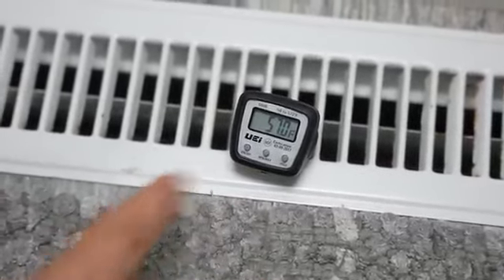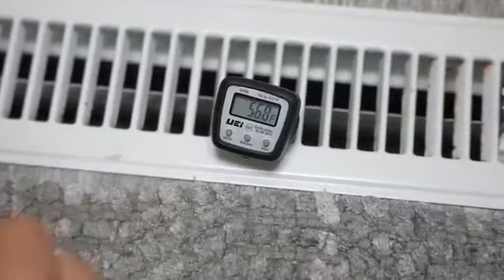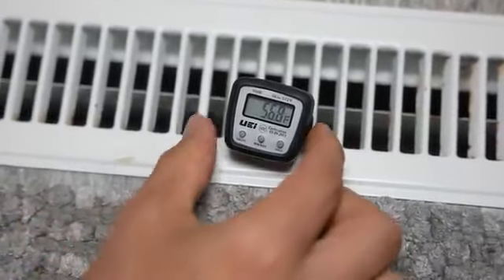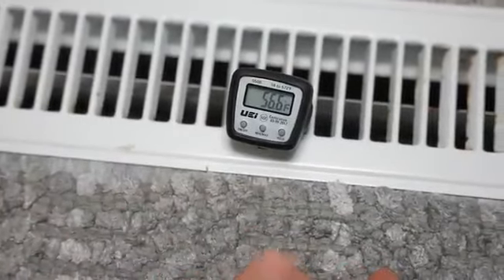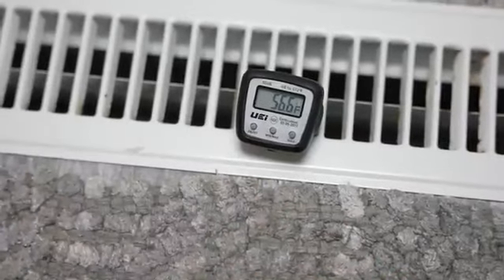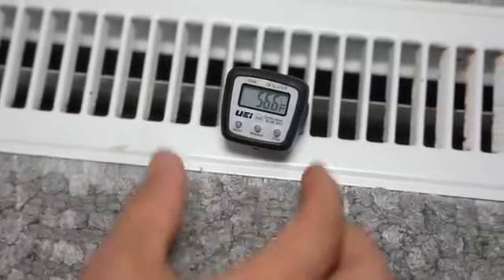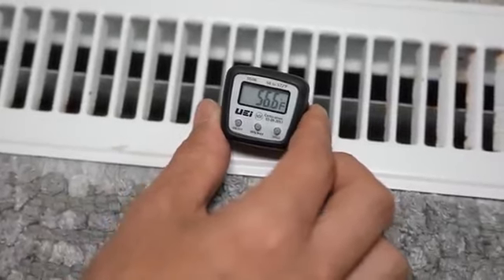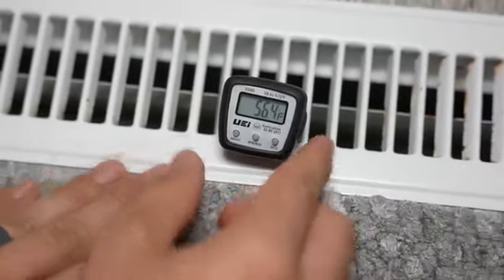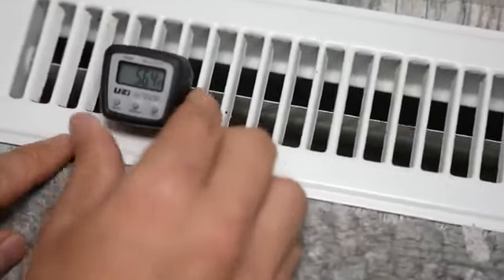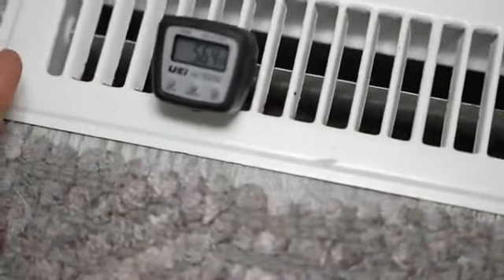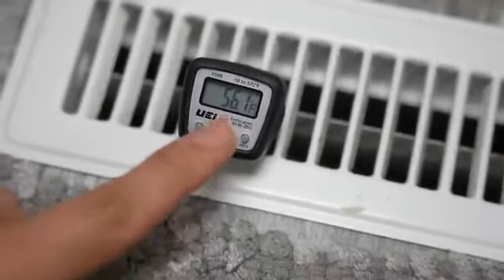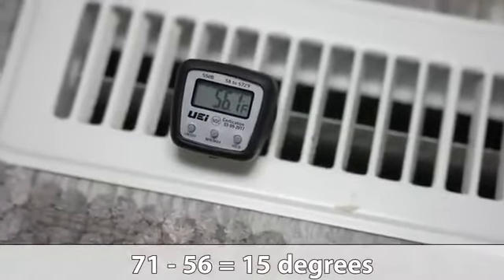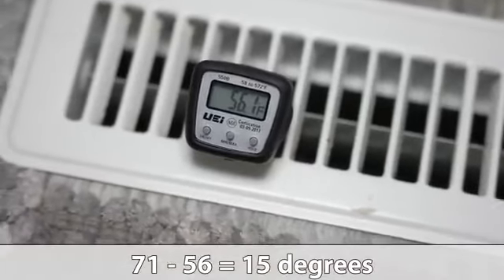But just because we're not at our 15 degrees, that doesn't quite mean that this is bad yet. You have to take a few different readings in a few different spots. So you can try a few other vents or maybe the ductwork in the basement. Get a few different reads before you come to a conclusion. Let's see if this will make a difference, even if I just move this thermometer over here, because sometimes the airflow is a little bit stronger on the sides of these vents instead of the middle. Okay, so I gave it another half a minute, and as you can see, we got down to 56.1. So we're exactly at 15 degrees.